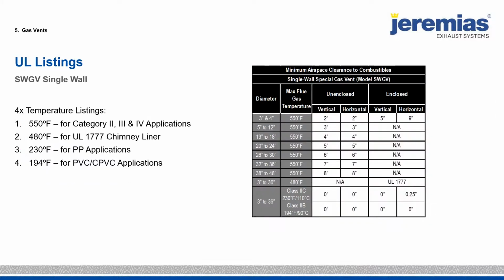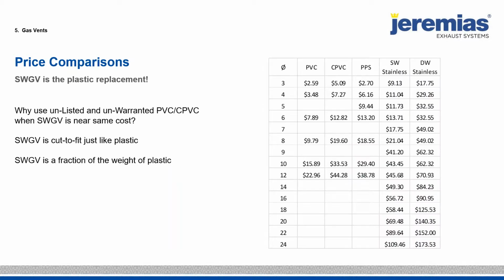So the single wall, again, includes the plastic applications. So you have a 0 clearance to combustibles, except for the PP on the enclosed horizontal. So we think this is important because we see more and more areas not allowing non-listed PVC, CPVC used for venting. I want to point out that maybe at 6-inch diameter, the single wall stainless, which includes a distributor markup, is nearly the same cost as PPS and CPVC. And the larger we go, the larger diameter stainless looks more and more important.